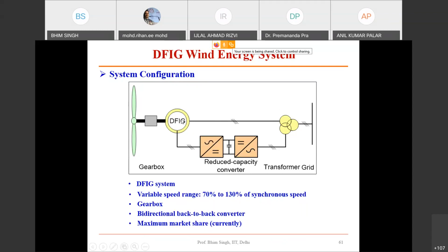One benefit, the machine efficiency is improved. You are generating 150% power, but the losses correspond to 100%. That is one reason. Another is that the converter rating is hardly 1/3. Here it could have been 210%, but you are keeping typically around 70% power rating only. So 1/3 is the converter rating. That is another benefit of it. And typically the speed range suits this purpose very well also.